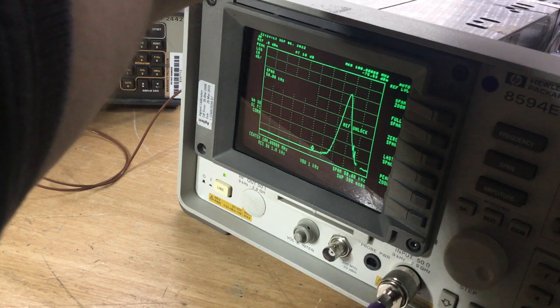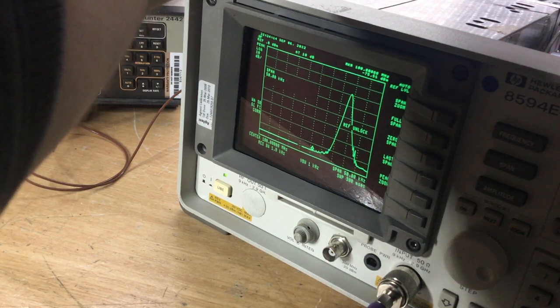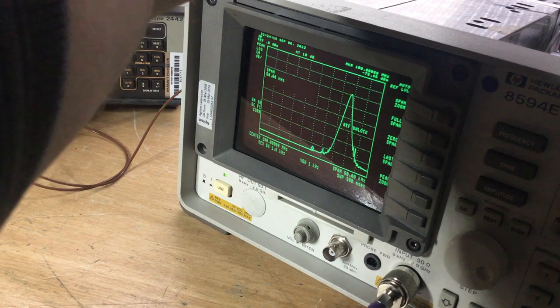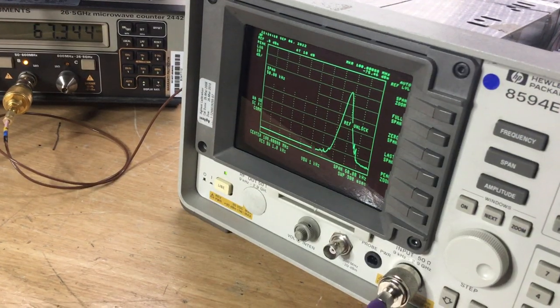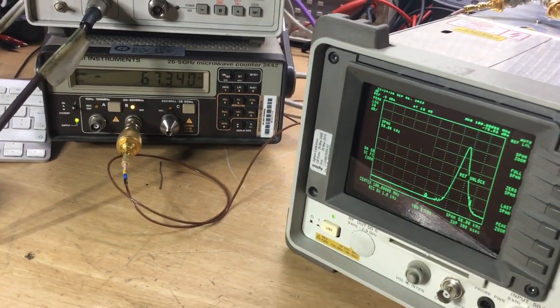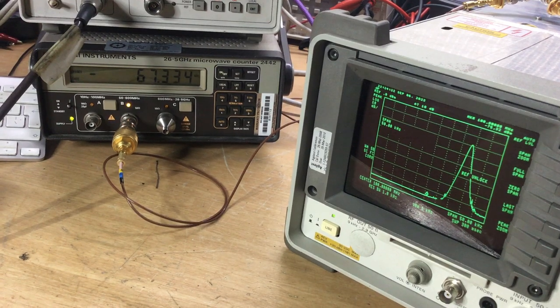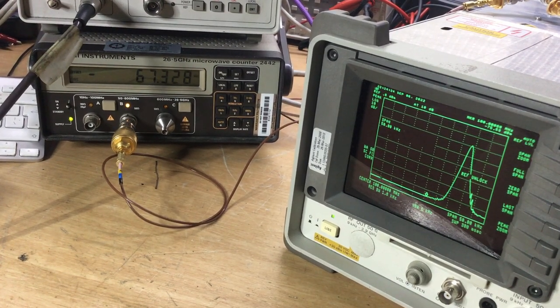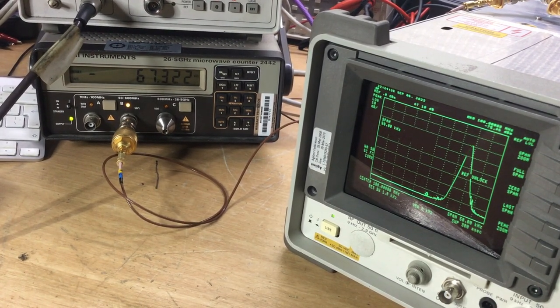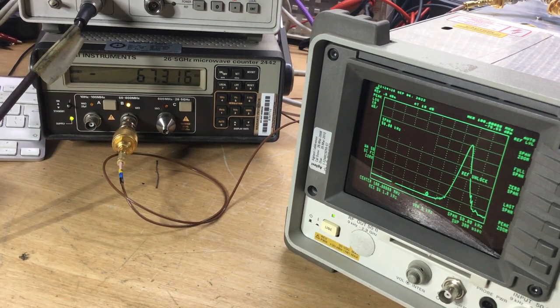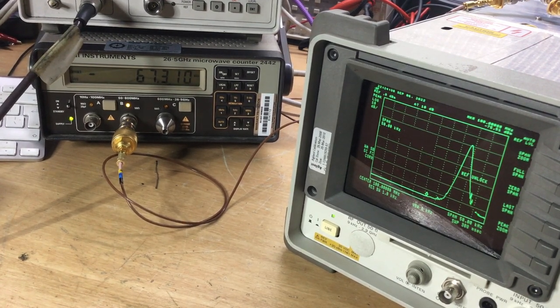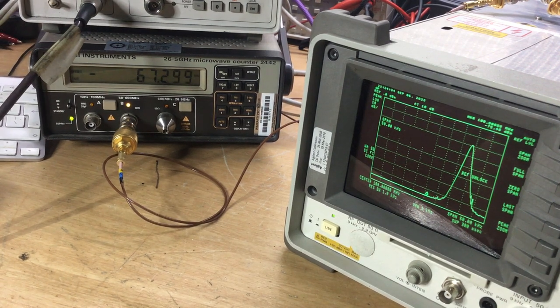And then that's fully counterclockwise, so that's the minimum that I can achieve, which according to the measurement from the frequency counter, it's off by about 67 kilohertz. So we might have to just turn the instrument on its side again and then adjust the 10 megahertz oscillator to see whether or not that will pull it in.